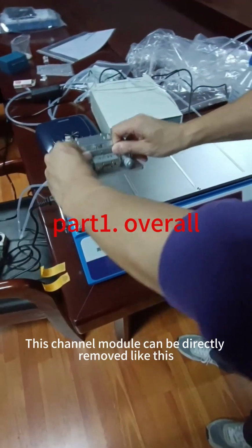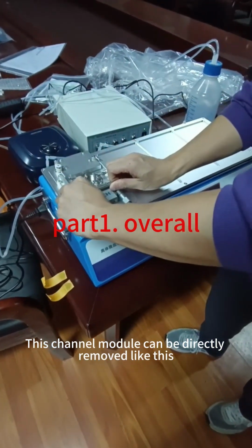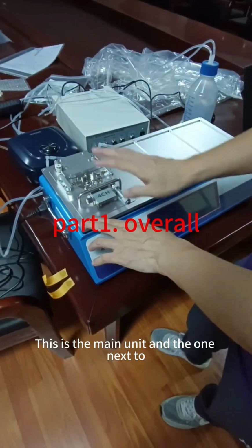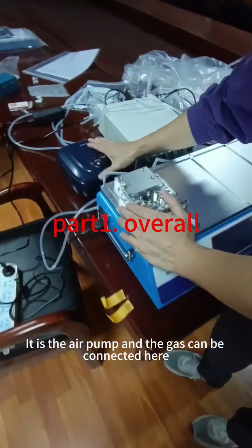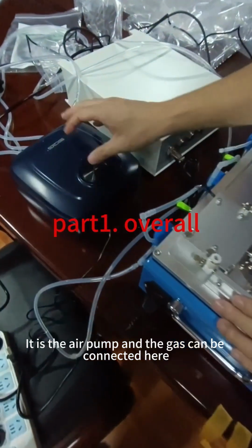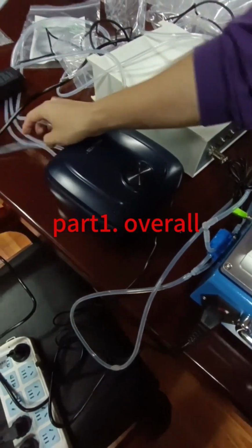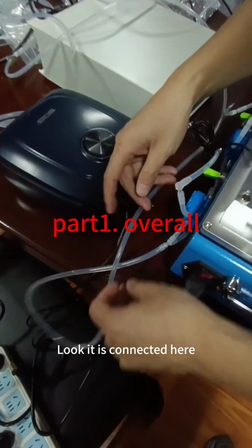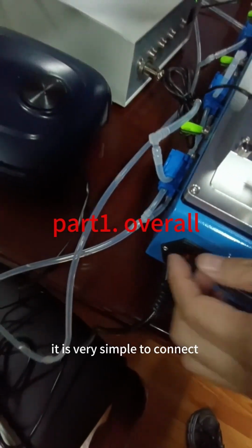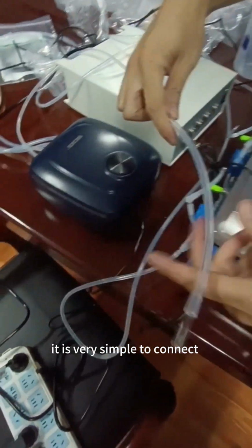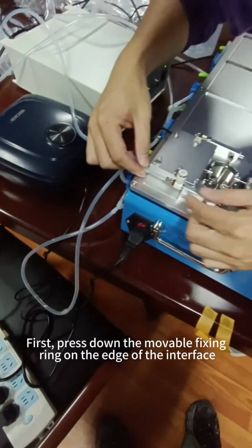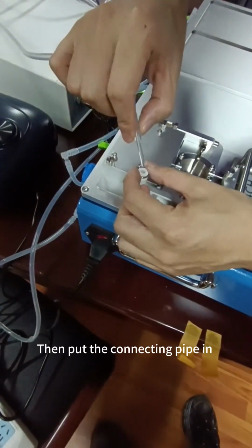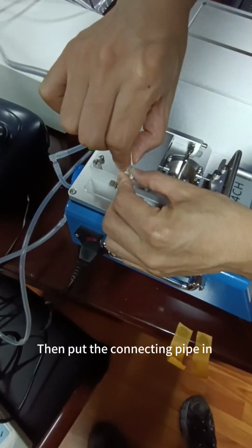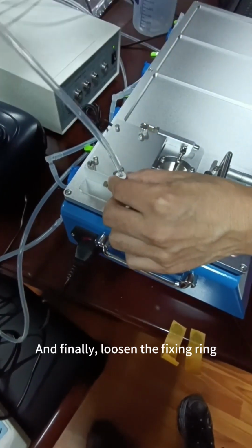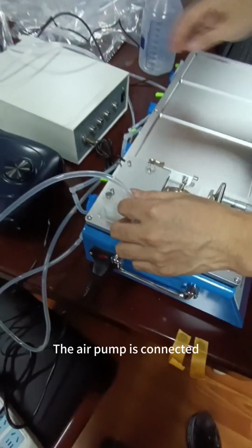This channel module can be directly removed like this. This is the main unit, and the one next to it is the air pump, and the gas can be connected here through the pipe. Look, it is connected here. It is very simple to connect. First, press down the movable fixing ring on the edge of the interface, then put the connecting pipe in, and finally loosen the fixing ring. The air pump is connected.